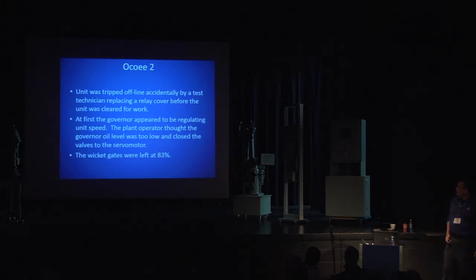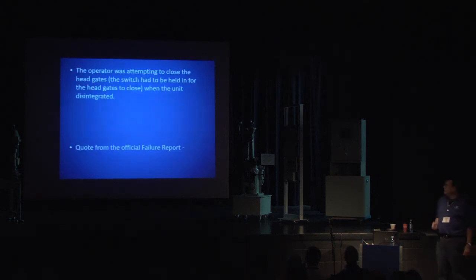And then this was really bad. When he thought the governor oil level was too low, he closed the valves to the servo motor, so the wicket gates were left pretty much wide open. So the governor was doing what it was told to do. The unit ran away, and the operator couldn't get down to turn the oil back on to close the wicket gates, so he was trying to close the head gates instead.